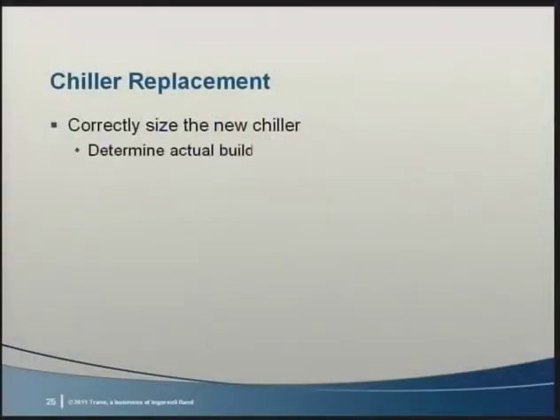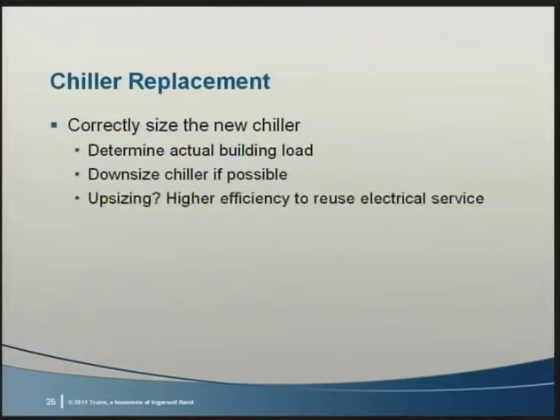When considering a chiller replacement, first figure out what size chiller is needed. Don't just replace a chiller with the same capacity new chiller. If the load is reduced enough, you may be able to switch to a different style of chiller to meet budget or space constraints. Now, I talked about building changes that reduce the loads. What about system expansion? There may be times when the load has increased. In these cases, one of the challenges may be reusing the existing electrical system. Efficiency can help you here.